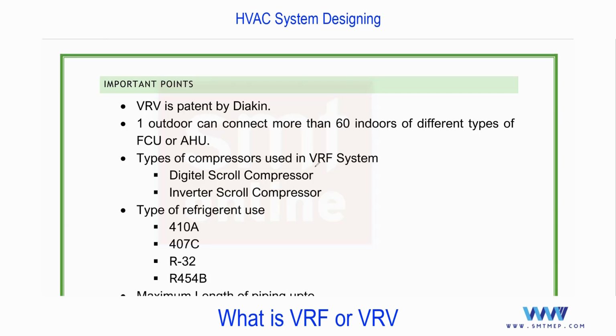Next, you see type of compressor. This is also important in VRF. Not only in VRF, now in the market, even in split systems and chilled water systems, you'll find this type of compressor. But mostly the inverter compressor or digital compressor started with the VRF system, and now it's available in split systems also. When I use the term VRF, it includes VRV also; I'll not repeatedly use both terms. The types of compressor are the digital scroll compressor and the inverter scroll compressor.